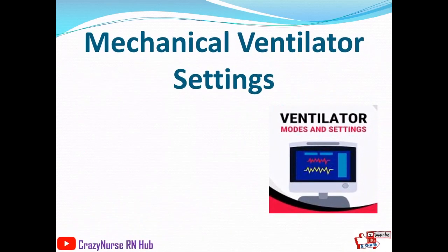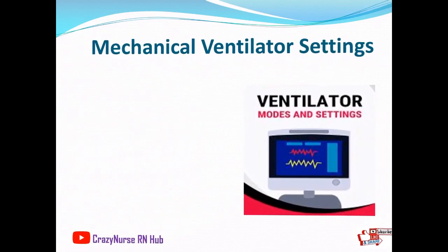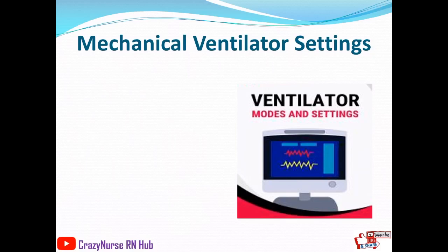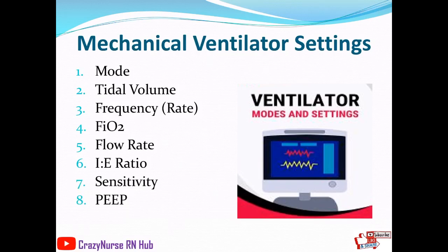Now let's proceed to mechanical ventilator settings — controls on a ventilator that can be set or adjusted to determine the amount of support delivered to the patient in the form of ventilation and oxygenation. The different settings include: mode, tidal volume, frequency or rate, FiO2 (fraction of inspired oxygen), flow rate, I-to-E ratio, sensitivity, PEEP, and alarms.